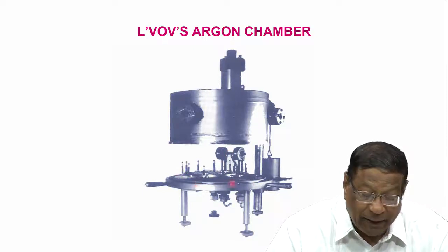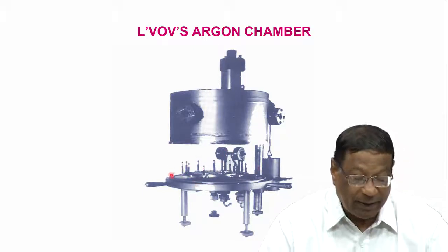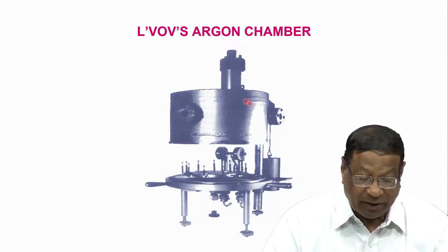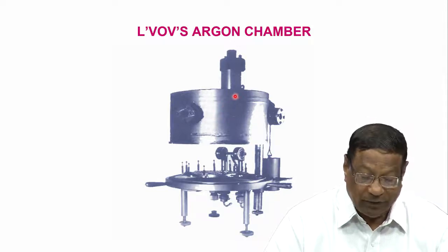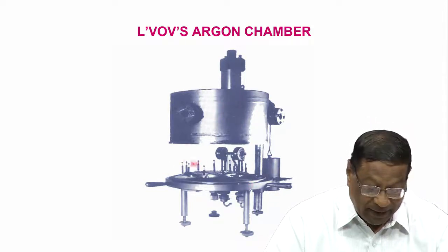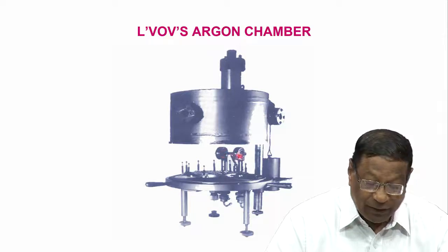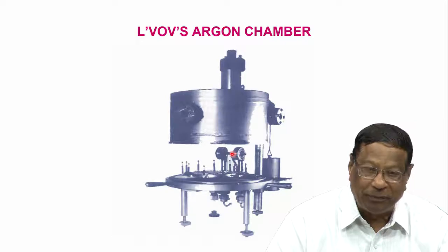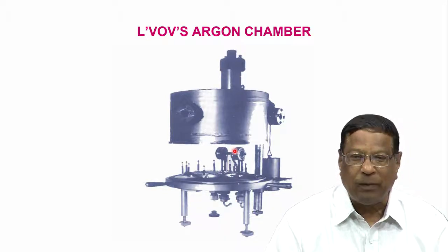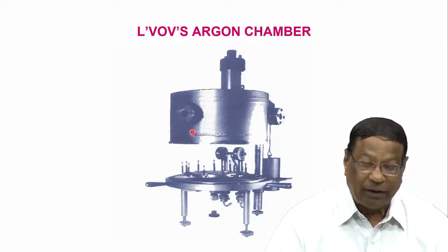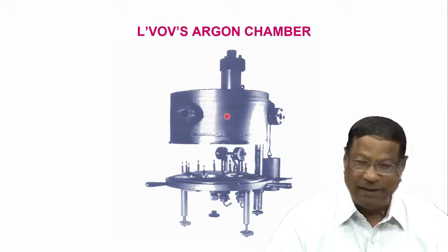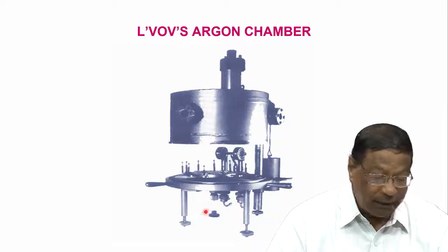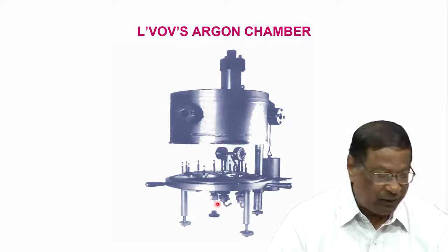these are the guide pins, and this is the base plate, and then this is the cover for this. So, this cover moves and sits exactly in this, so that it does not disturb or touch this graphite tube. Okay, it is just basically a small circular chamber, which is airtight.